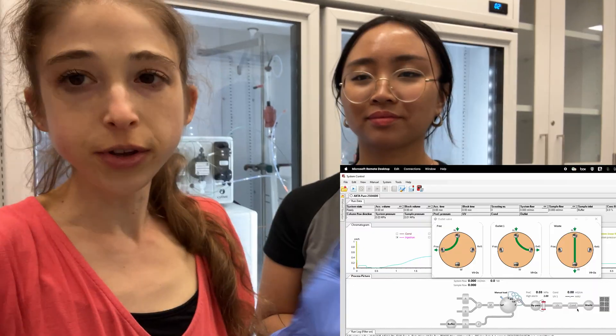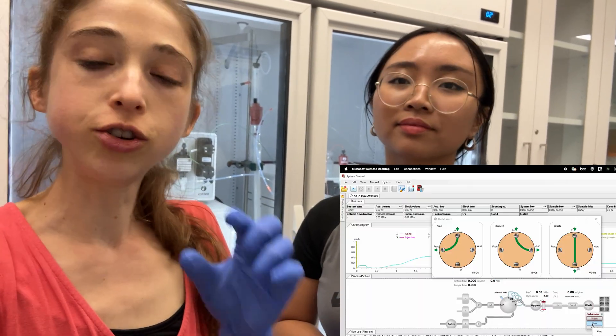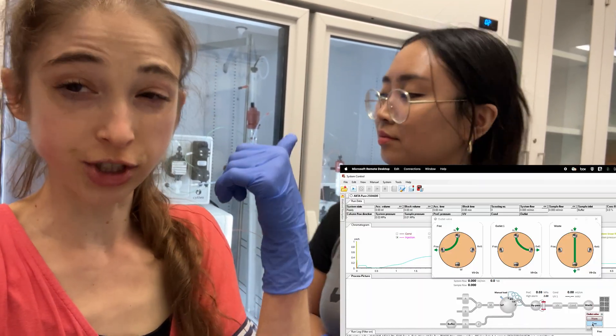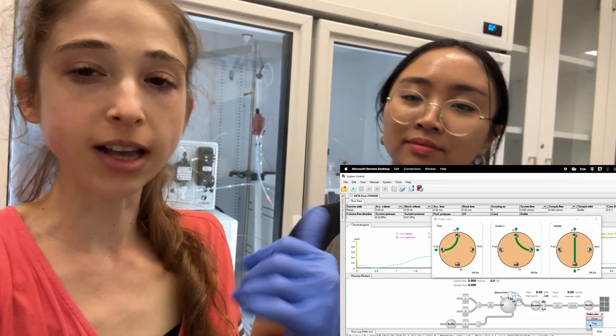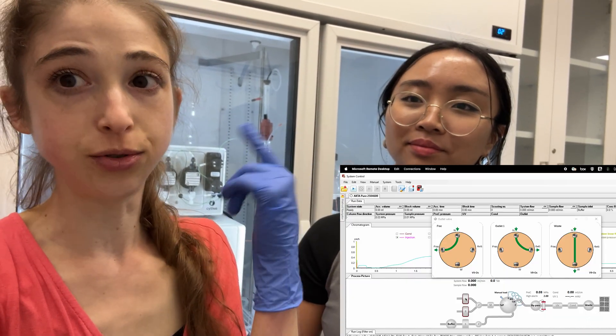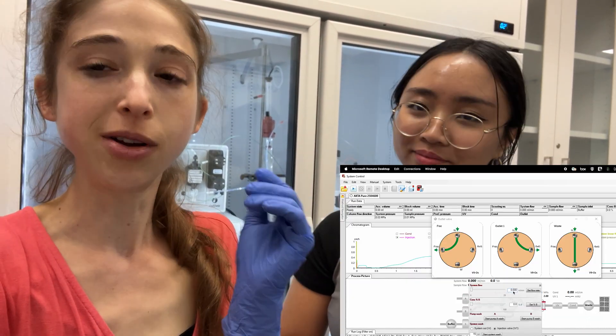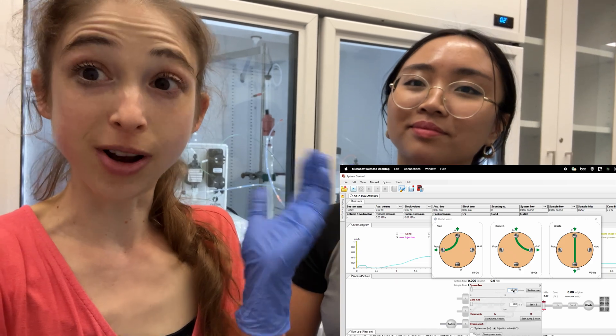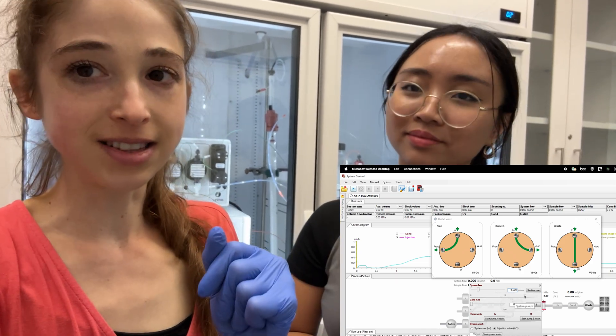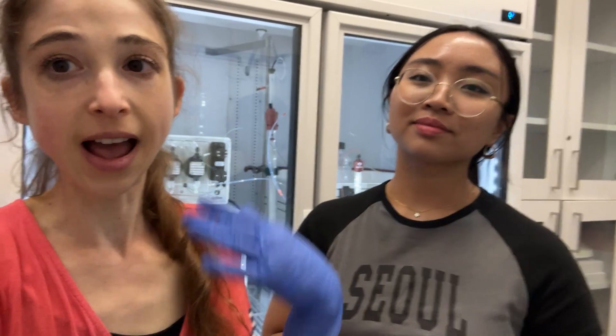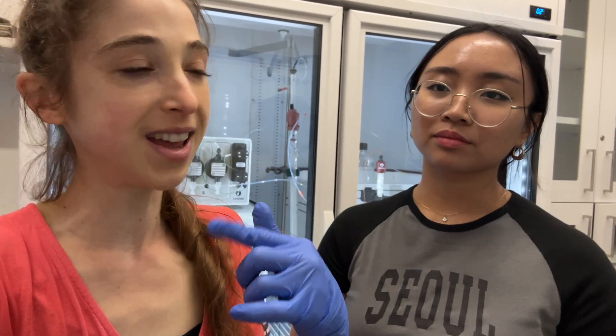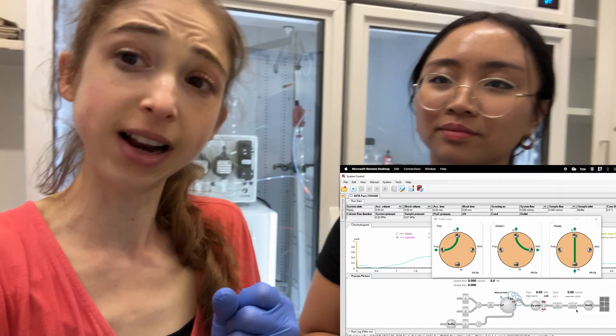So you want to do this washing after every run. You should go ahead and make sure that you're washing that main line, that main tubing, as well as you're washing the line to the fraction collector. And so you're going to want to wash that with water. And then if you are doing something longer term storage, you can go ahead and after you do the water, then do ethanol. And then remember to do water again before you do anything with salt because the ethanol will precipitate it out.